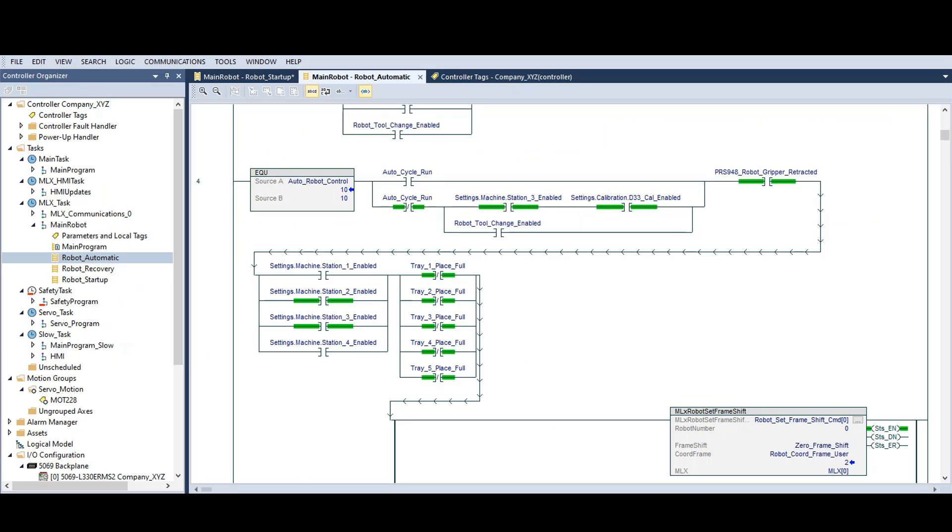It's usually easy to see in the ladder where the logic has stopped. Just look for the current step number. For this ladder, the auto robot control was stopped on step 10. Note that the set frame shift command was enabled but it's not completing.